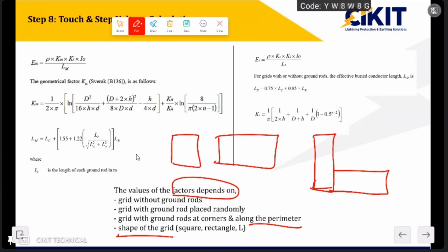So if it is a square, what will be the value of n? If it is a rectangle, what will be the value? If it is an L shape, what will be the values? If I'm having a square grid with earth electrodes only on the perimeter, then what will be the value? If I'm having a square mesh with earth electrodes only at random places, not providing them on the corners, then what will be the value of the parameter? So they have provided a detailed explanation for each and every different connection configuration also.